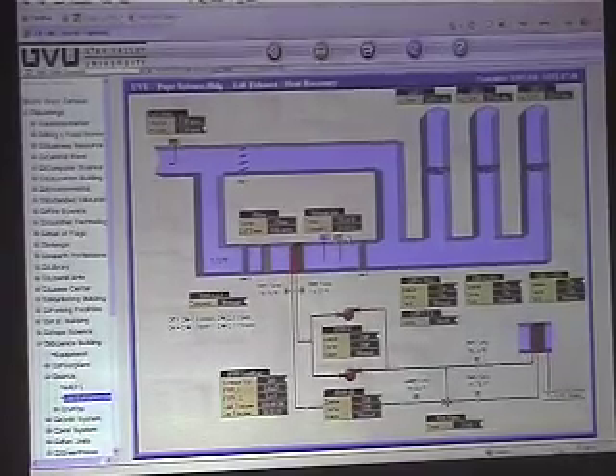Evap setup, once it enables for the day, it stays on until the end of the day, or if the outside air temperature gets below 50. So that way we're not running that thing just because the day hasn't expired yet and driving our discharge air down to a point that's too cold.